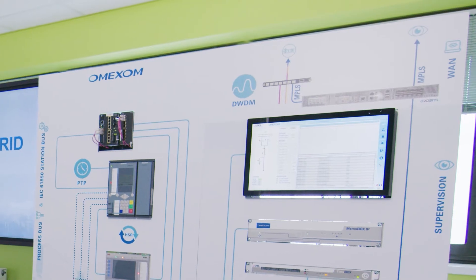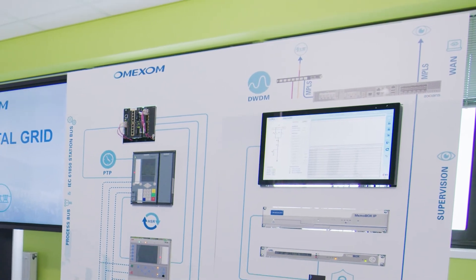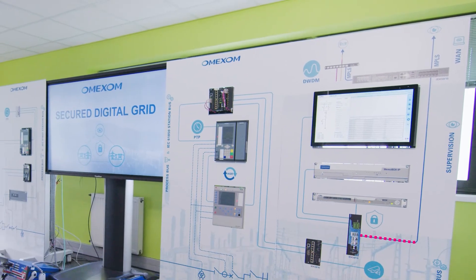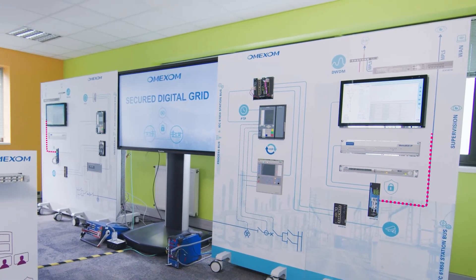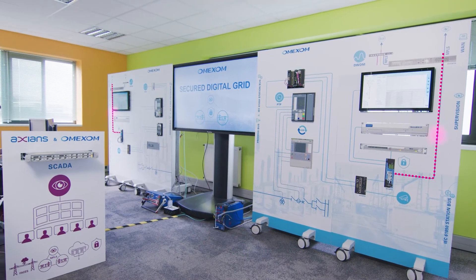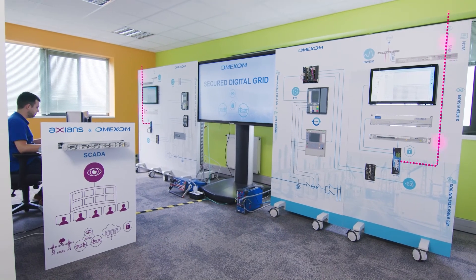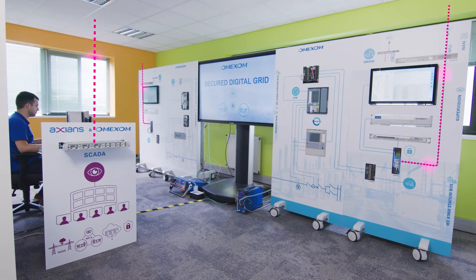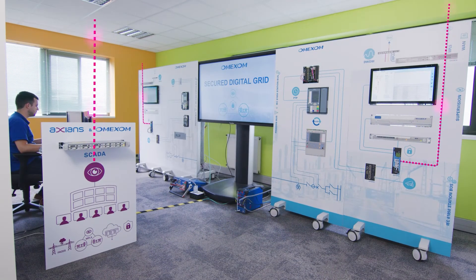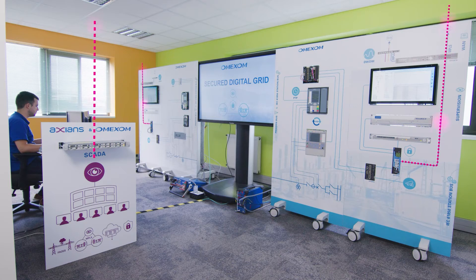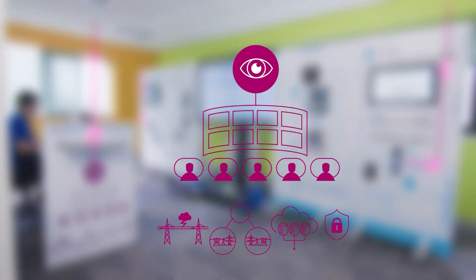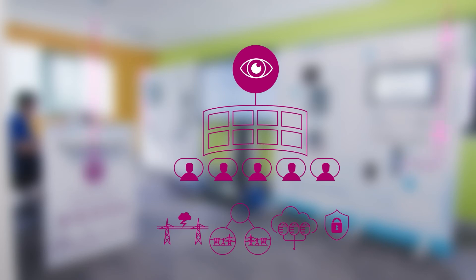To connect the substations and the control center, a next-generation utility network has been implemented. It relies on IP MPLS protocol to ensure continuity for critical applications, such as SCADA and teleprotection, or legacy services, while extending the support for standard applications.